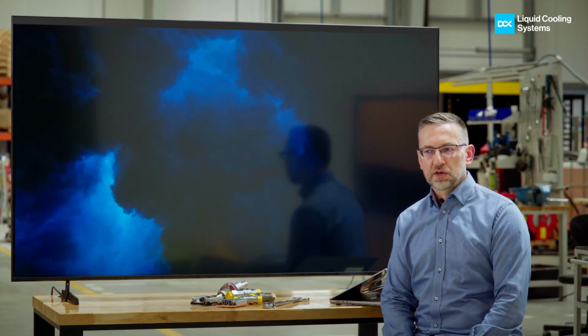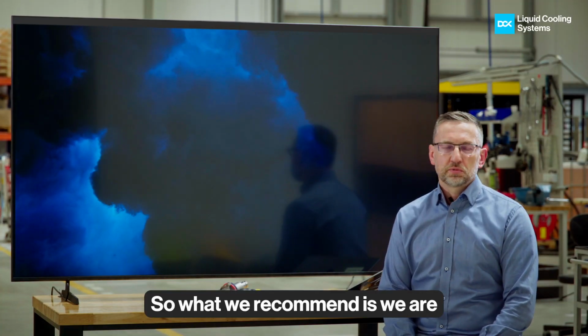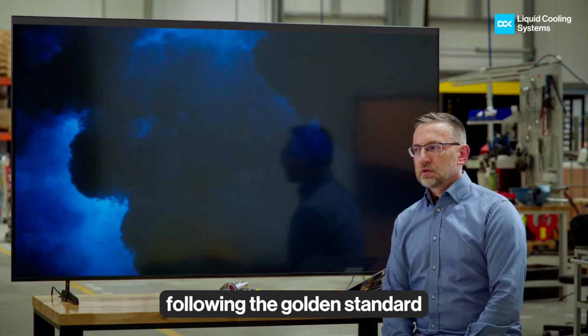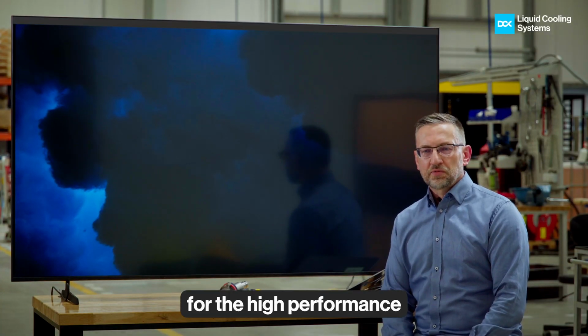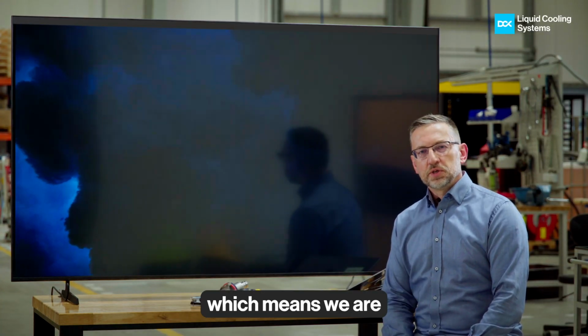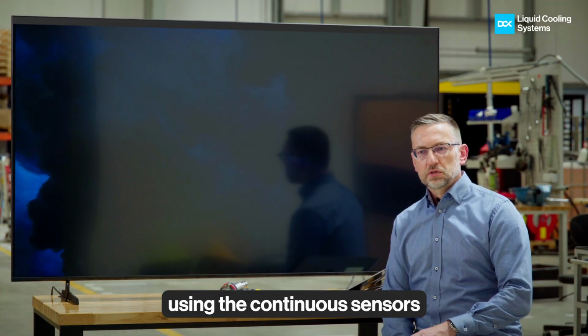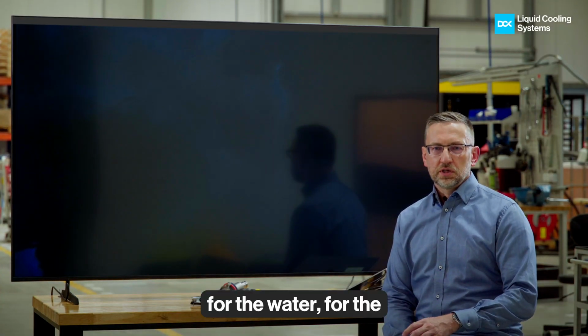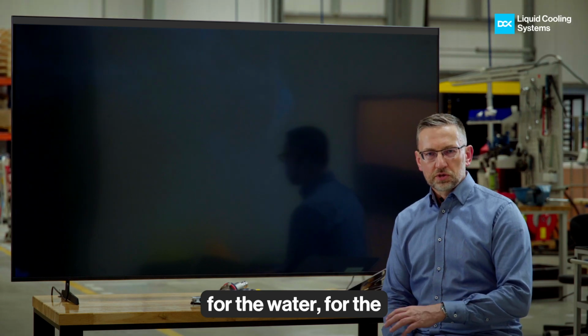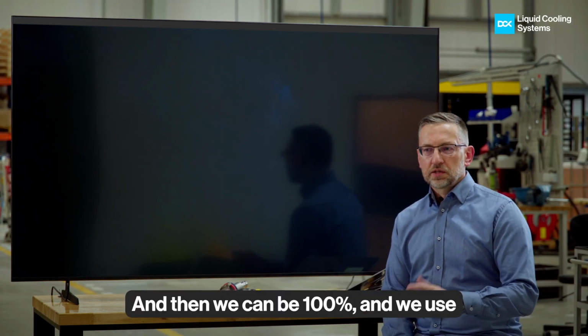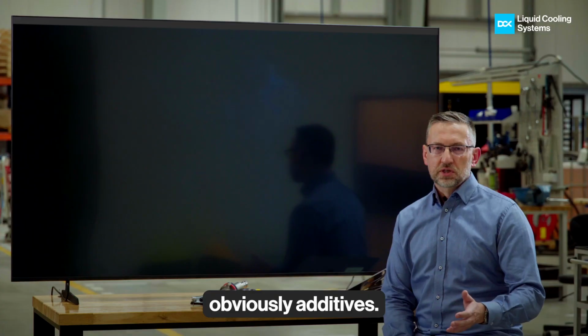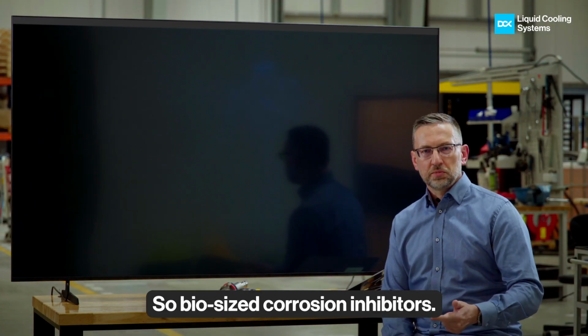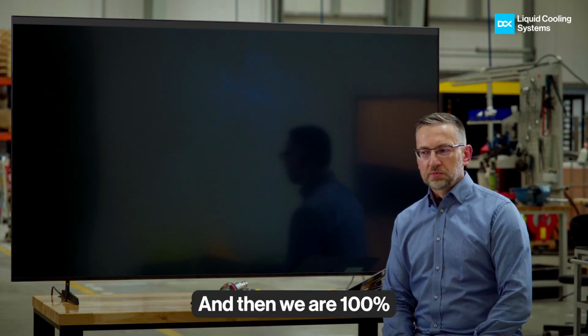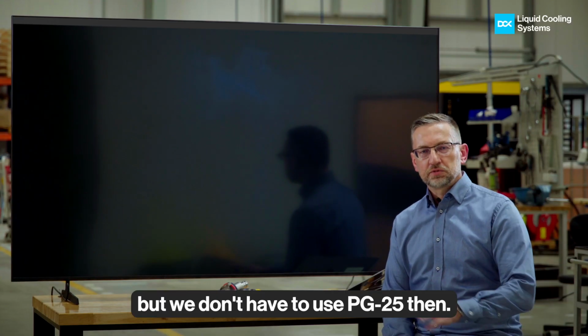What we recommend is following the golden standard for high-performance computing liquid cooling systems: using continuous sensors for the properties of the water, and using additives — biocides and corrosion inhibitors. Then we can be 100% sure we're biostatic, but we don't have to use PG25.